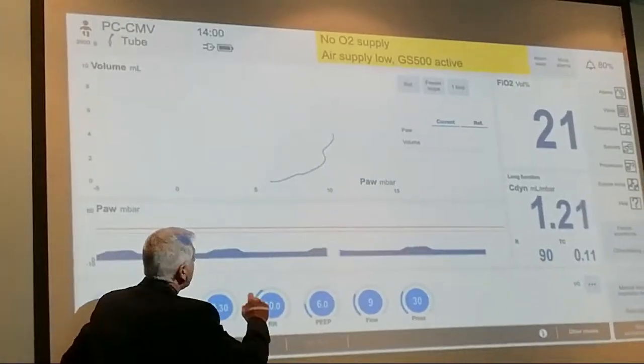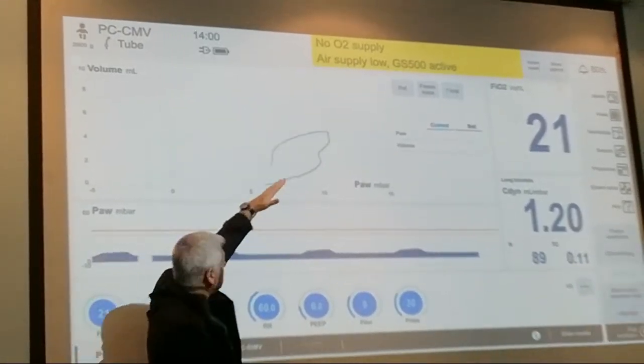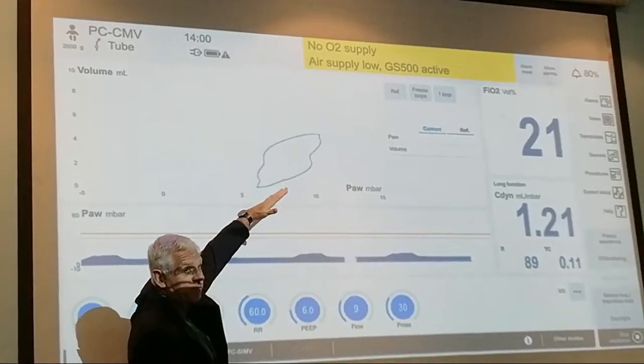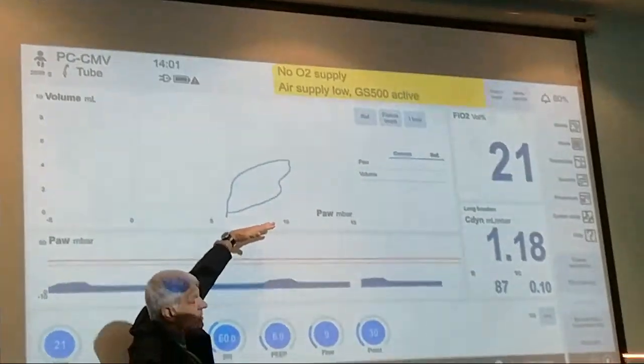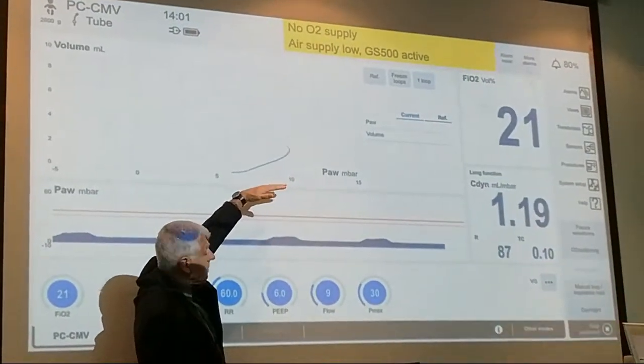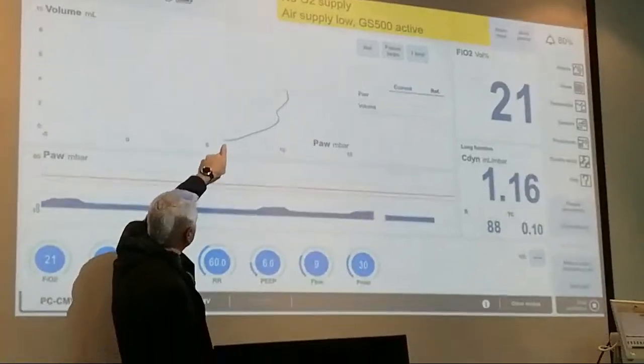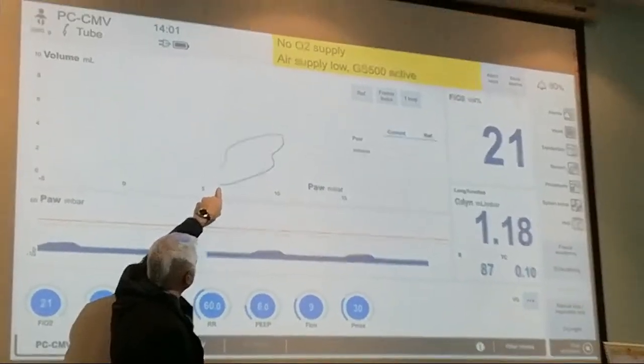this is the volume pressure loop. What you want to see is usually the angle of that loop should be about 45 degrees. If the angle becomes less than 45 degrees, it means the compliance is worse. You also want to see the opening pressure here. You shouldn't see a very flat part here.